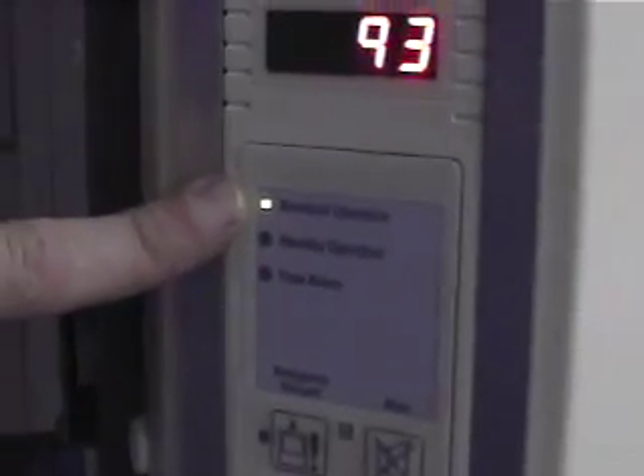You can see right here it says standard operation. That light is lit up. That means that this motion sensor has seen somebody in the last little while. If we keep people far enough away from it for long enough, it can go to setback, as long as they have that set up, which with these, that's typically how they get set up. And then it would attempt to maintain 60 feet per minute across there, minimum. The only difference with that is if you have it closed, it's already down at its minimum. So typically it's just going to maintain that 100 feet per minute even if it goes to setback when it's closed. The setback is really when somebody leaves it in a different position.